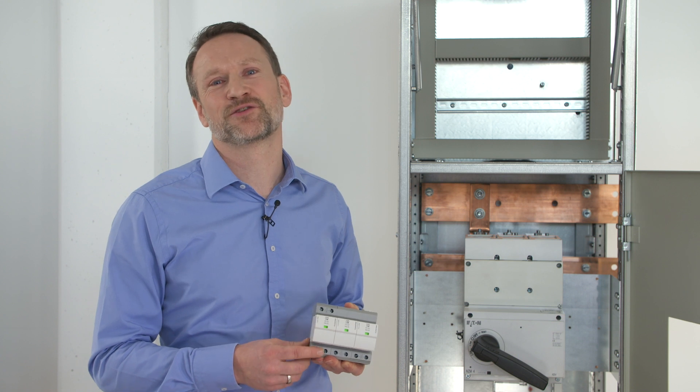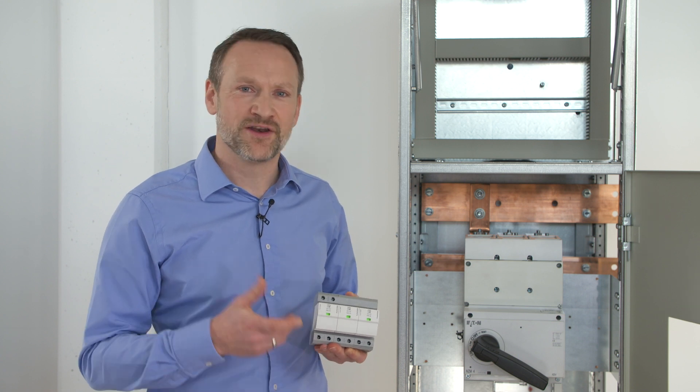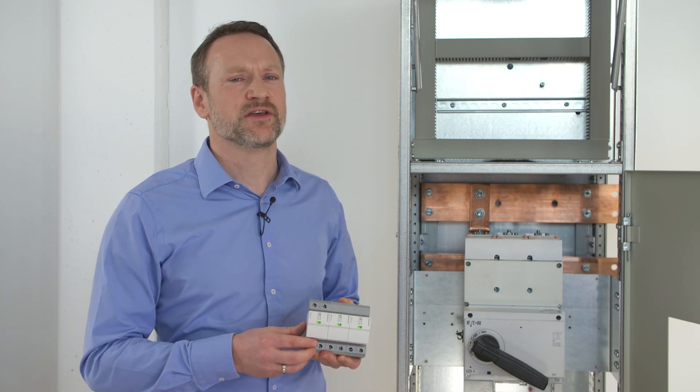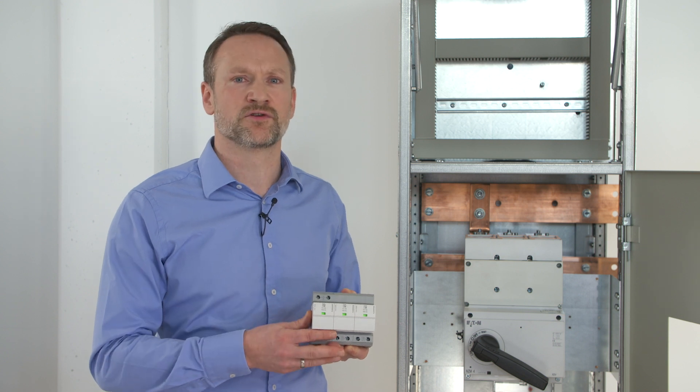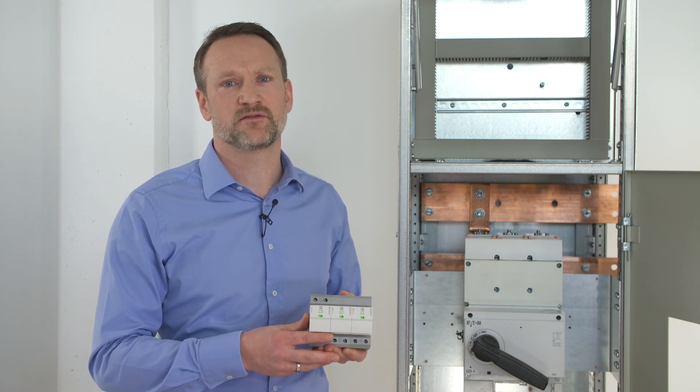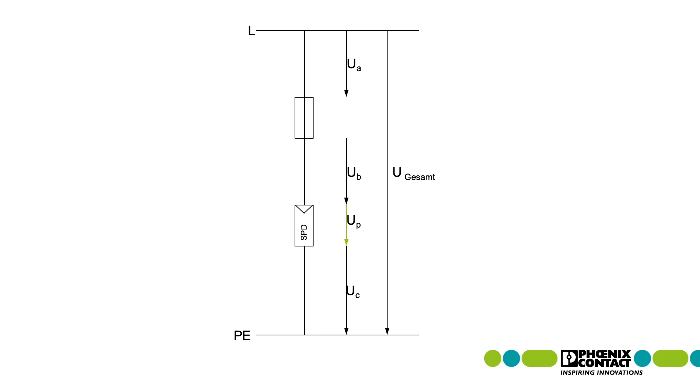Regarding cable lengths, it is the details that are most difficult. To protect the system effectively, it is not only the printed voltage protection level of the protective device that is relevant. It is also the voltage that drops via the cables during discharge.